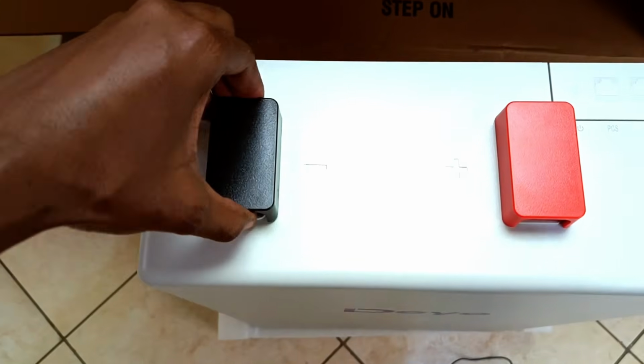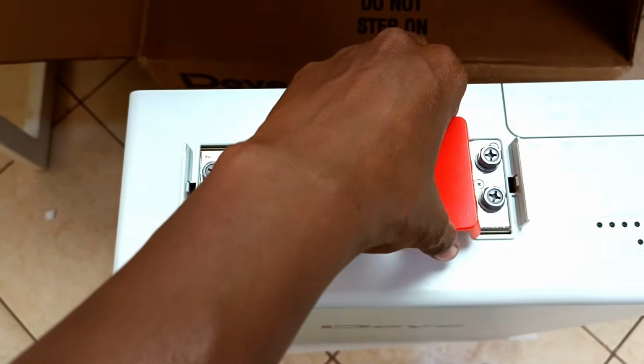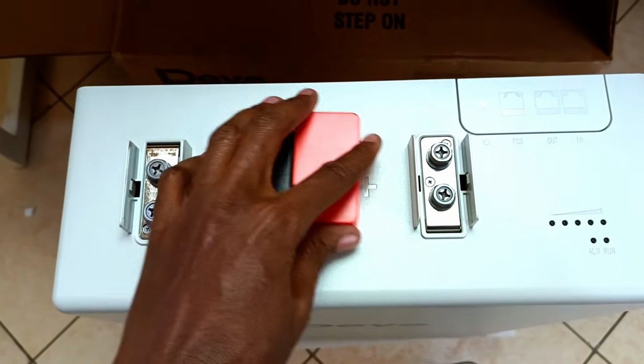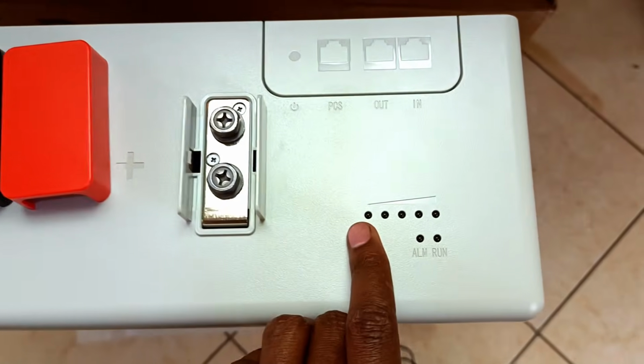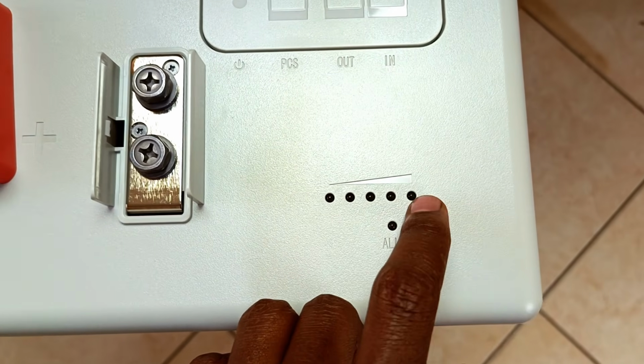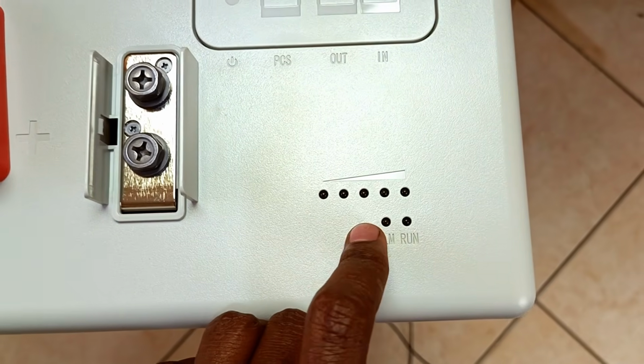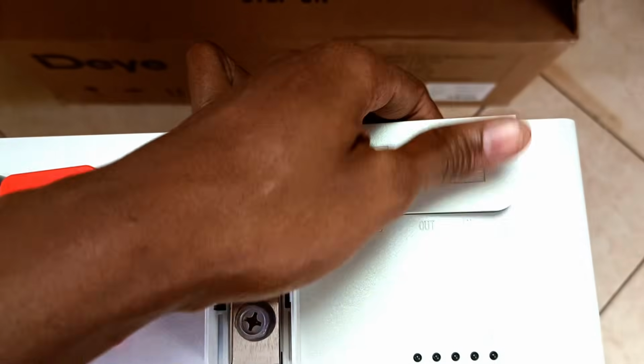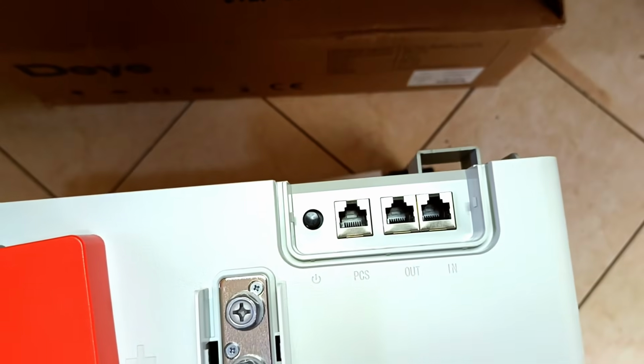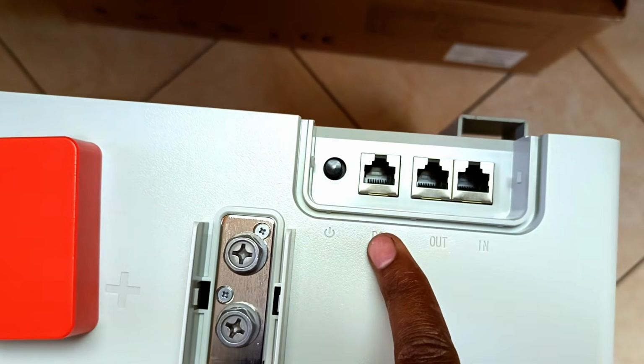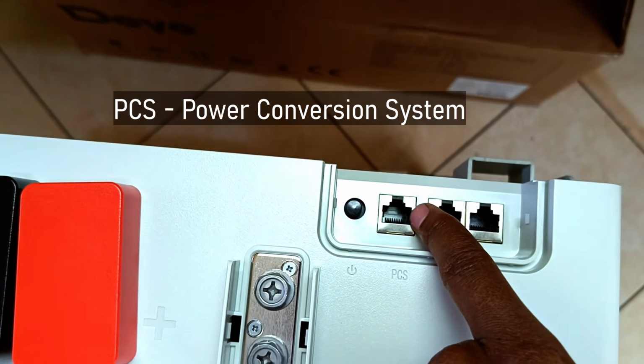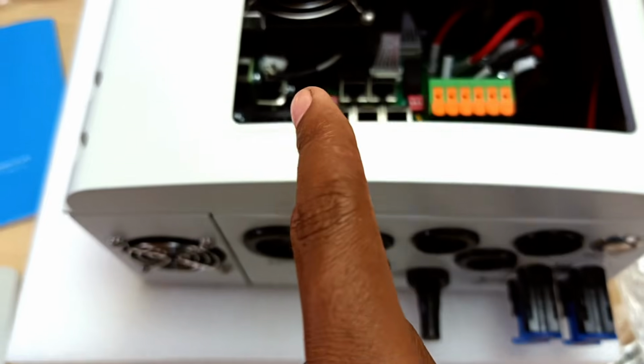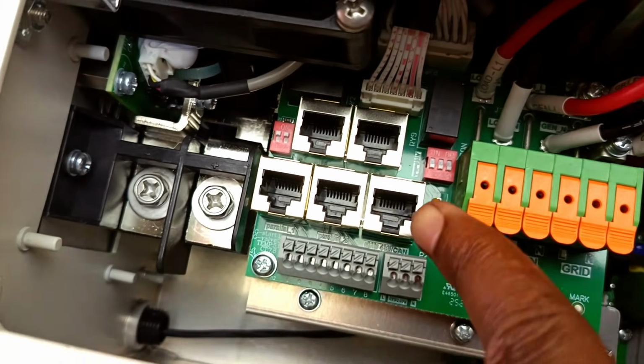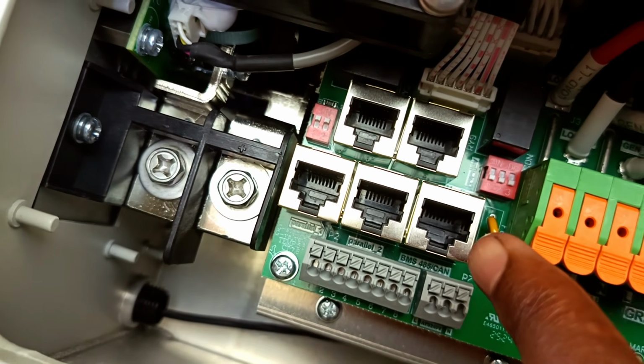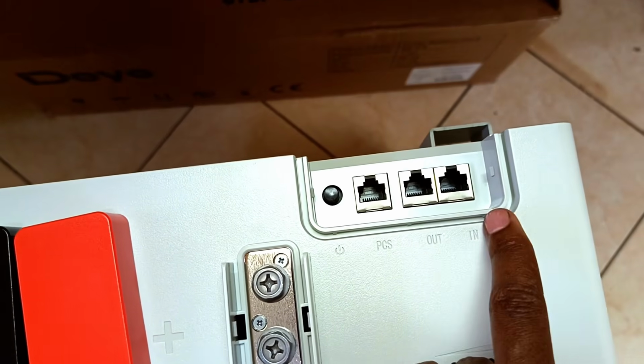Let's take a look at these ports. These are the battery terminals for the negative and positive terminal. These are the notification lights for state of charge, the alarm as well as the run light. And here are all the communication ports as well as the power button. This PCS port is what is supposed to be connected to the inverter directly, to this port here labeled as BMS or Battery Management System. The other ports are for connecting the batteries together.